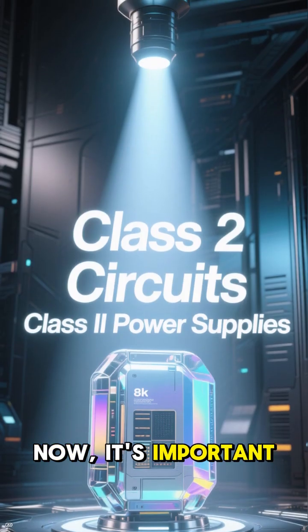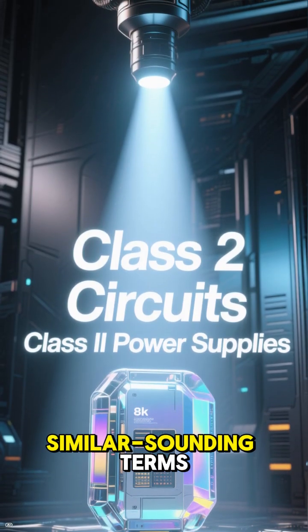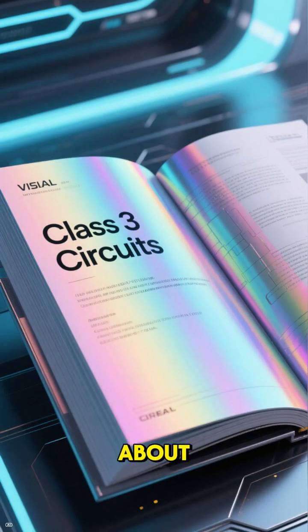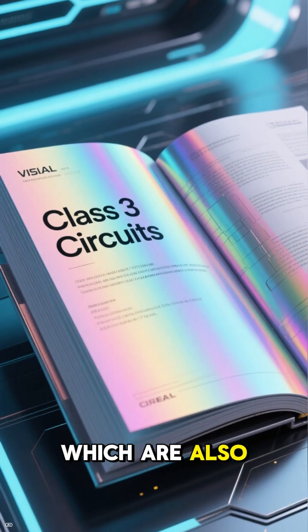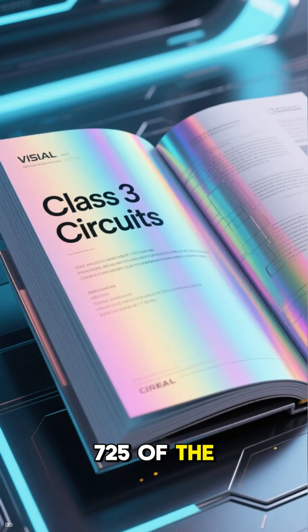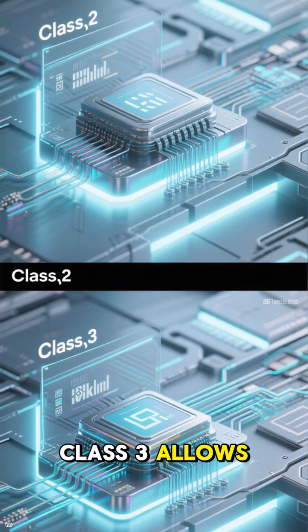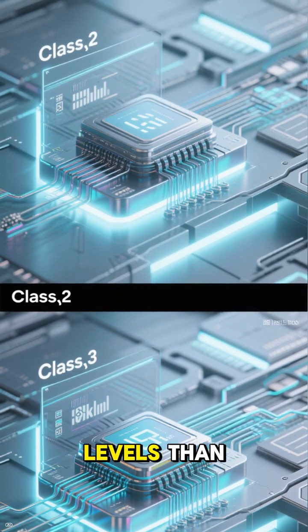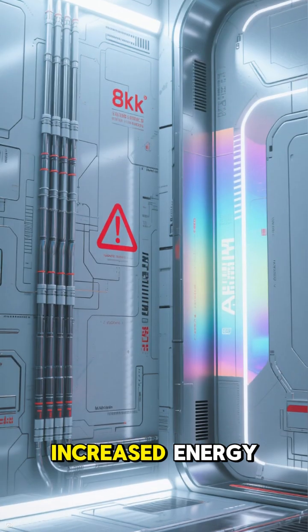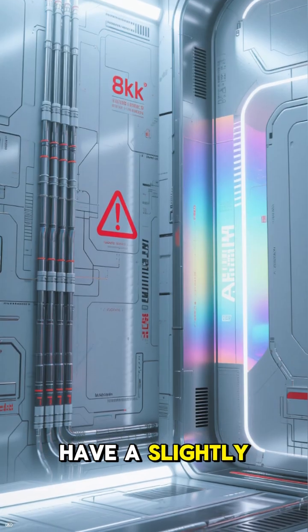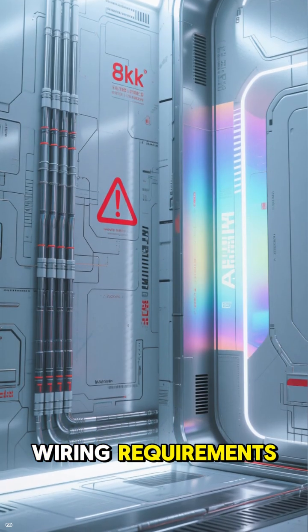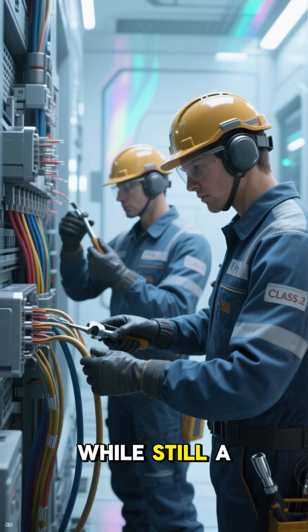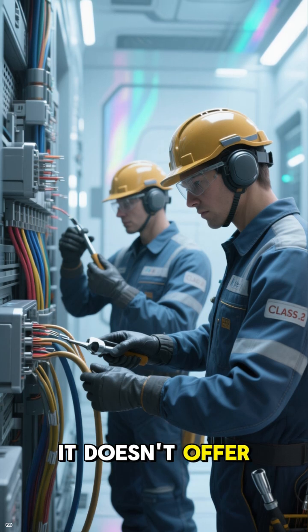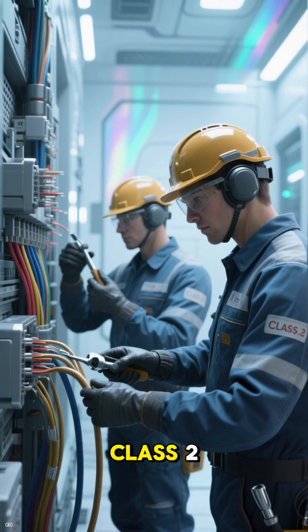Now, it's important not to get confused with a couple of similar-sounding terms. You might hear about Class 3 circuits, which are also covered in Article 725 of the NEC. Class 3 allows for slightly higher voltage and power levels than Class 2. Because of this increased energy, it's considered to have a slightly higher risk, and so the wiring requirements are a bit stricter. While still a low-voltage circuit, it doesn't offer quite the same ease of installation as Class 2.